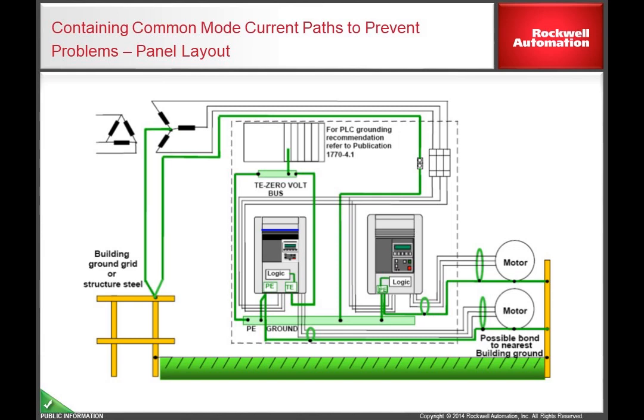Once this noise is routed back to the drive, it is equally important to minimize the chance of this current coupling onto sensitive devices within the same enclosure. Containing common mode current begins with good grounding and bonding practices. The motor should be bonded to the drive ground and the drive ground should be connected to the electrical system ground. If the drive is kept in an enclosure that is painted on the inside, be sure to scrape off the paint at the ground connection point to ensure a solid ground within the enclosure.